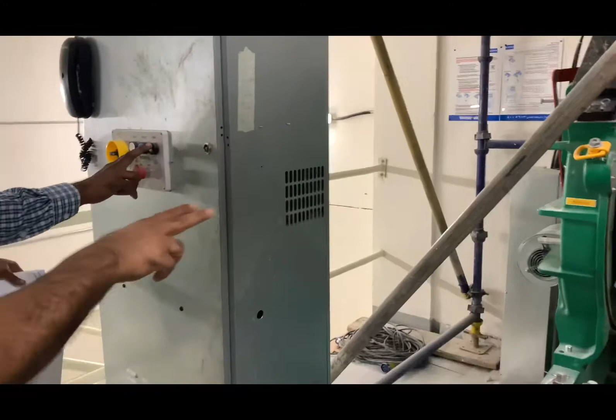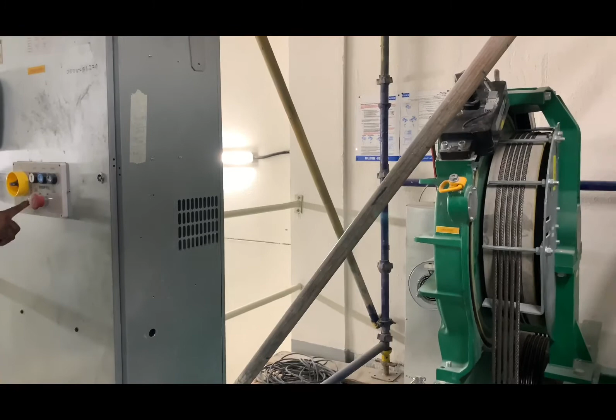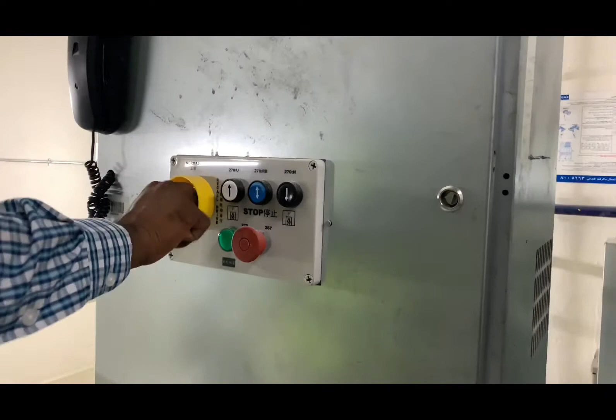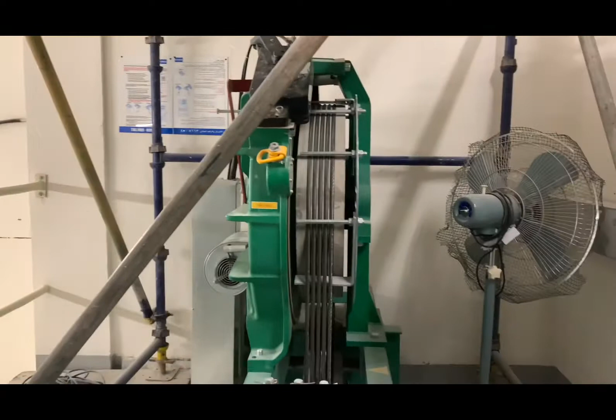If you are not doing proper commissioning, these two switches are used to drive the lift. Now it is in the inspection mode. You can see this is the recall drive. If I put the elevator this way, it is in normal run. In inspection I can run the elevator manually by hand. If I press these two buttons, the lift will go down. You have to hold this button, then only it will start to move down. If you press these two buttons, it will start to run in the up direction.